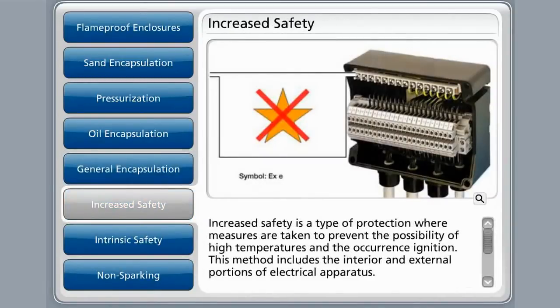Increased safety is a type of protection where measures are taken to prevent the possibility of high temperatures and the occurrence of ignition, including both interior and external portions of the electrical apparatus. The general application would include connection and distribution boxes, luminaires, measuring instruments, and devices that do not normally produce ignition during operation.